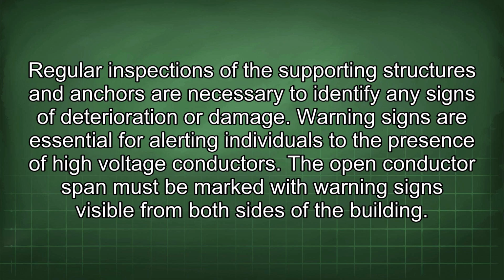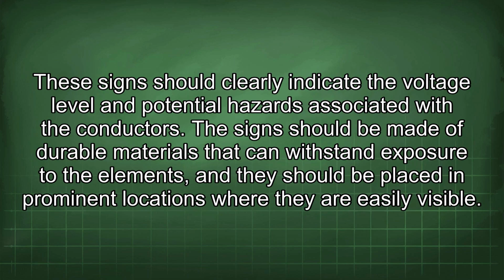Warning signs are essential for alerting individuals to the presence of high-voltage conductors. The open conductor span must be marked with warning signs visible from both sides of the building. These signs should clearly indicate the voltage level and potential hazards associated with the conductors. The signs should be made of durable materials that can withstand exposure to the elements, and they should be placed in prominent locations where they are easily visible.